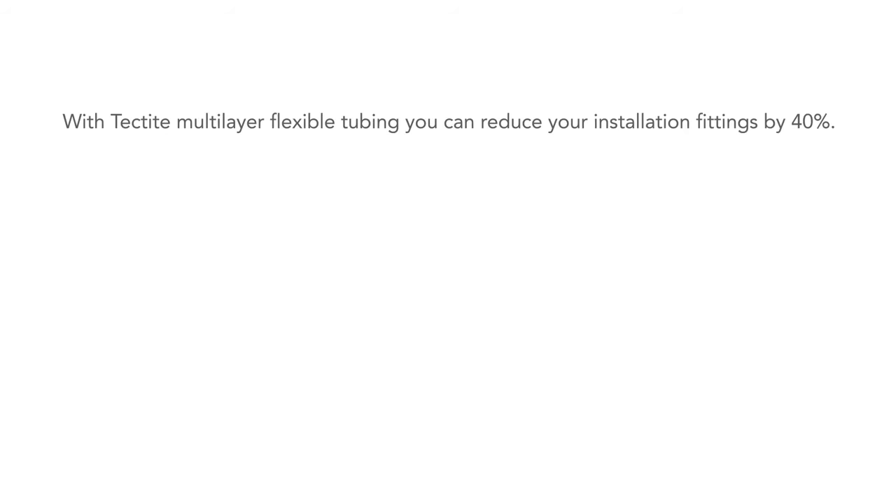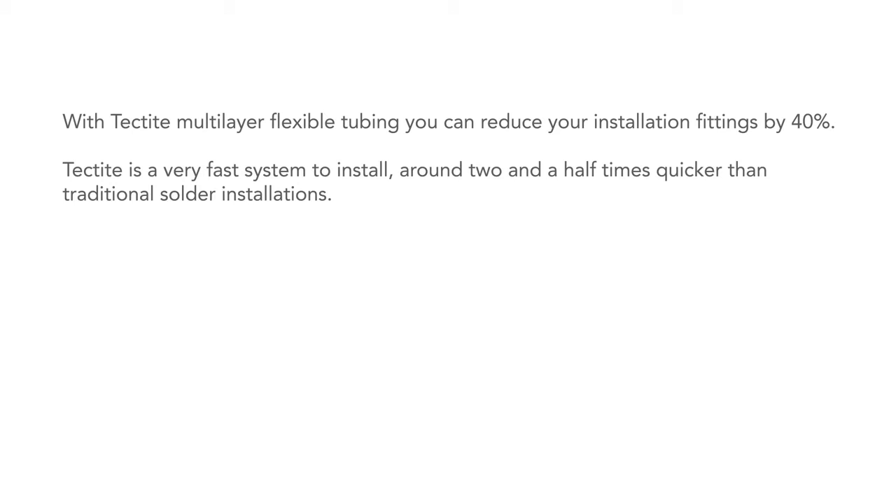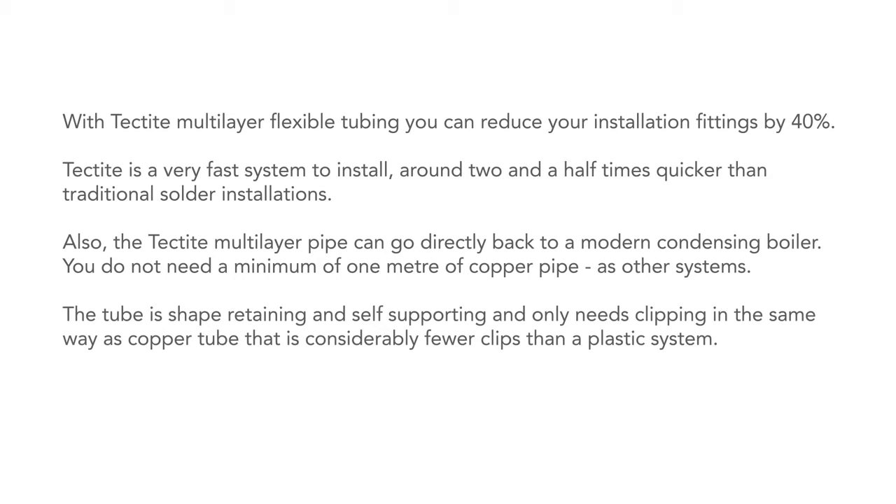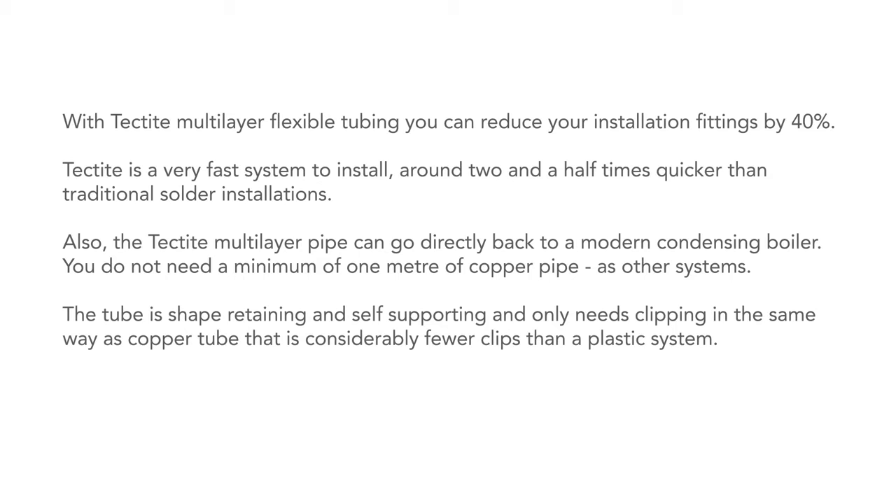Let's recap some of the key advantages of the Tectite system. With the Tectite multi-layer flexible tubing you can reduce your installation fittings by 40%. Tectite is a very fast system to install — around two and a half times quicker than traditional solder installations. Also, the Tectite multi-layer pipe can go directly back to a modern condensing boiler; you do not need a minimum of one metre of copper pipe as with other systems. The tube is shape retaining and self-supporting, only needs clipping in the same way as copper tube — considerably fewer clips than a plastic system. This all accumulates to some significant time savings in your installation.